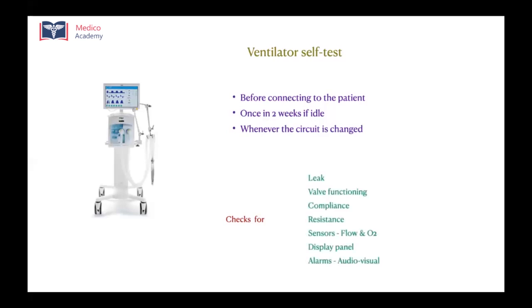It checks for any leaks in the circuit. If the valves in the ventilator are functioning fine. It also checks for the circuit compliance and resistance, because there are different companies which come up with different kinds of ventilator circuits. So the ventilator first checks what is the compliance and what is the resistance of the circuit so that it can compensate by increasing or decreasing the flow and other parameters. Then the ventilator also checks whether the sensors are working fine, whether the flow sensors or the oxygen sensors are working fine. It also checks the display panel. If the display is fine, are all the figures being illuminated properly, especially in the old digital kind of screens, whether all the parameters are being displayed.